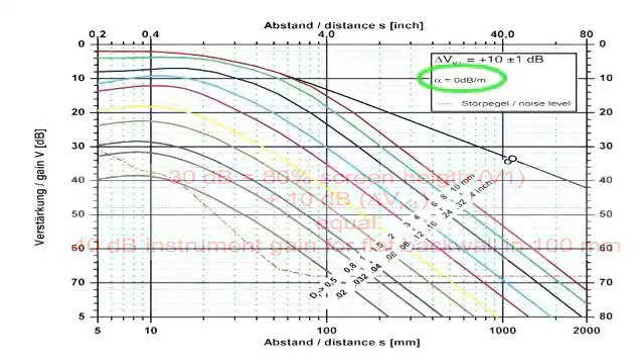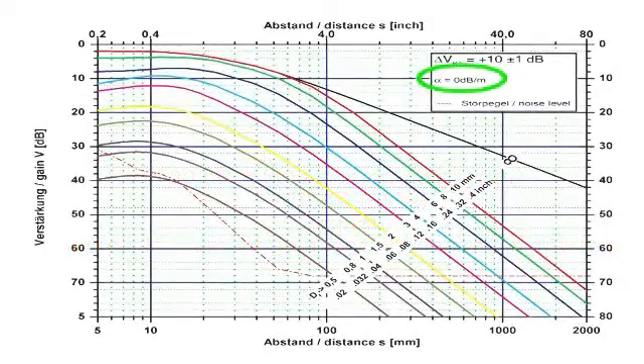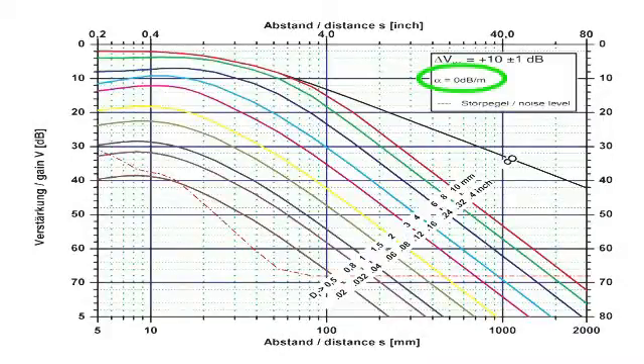One last comment regarding sound attenuation. On each of GE sensing and inspection technology's DGS diagrams, the remark alpha equals 0 dB per meter can be found. This means that the given diagram is only valid for attenuation-free test materials. Since this is an ideal assumption, the user is obliged to know the specific sound attenuation of the material they are testing and must correct all echo amplitudes if their material attenuation is not negligibly small.